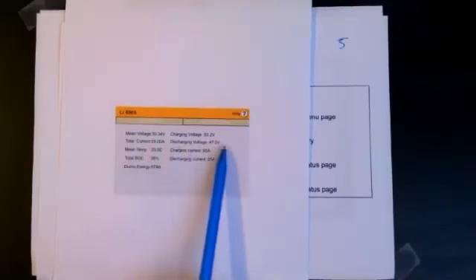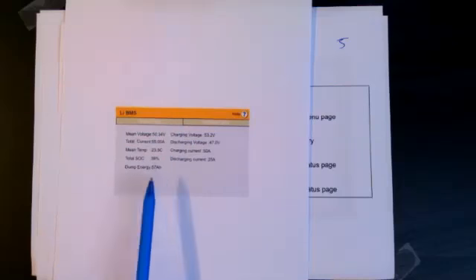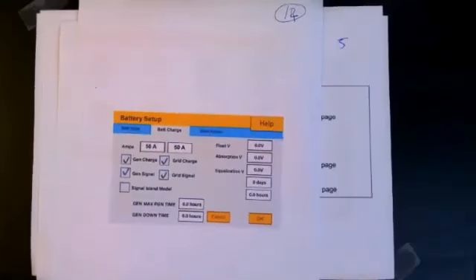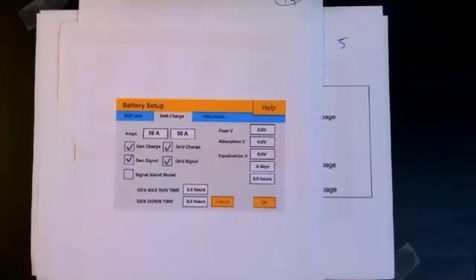You must make sure that you get something like this. You will see a very clear message, and this information is coming from the BMS, the battery management system. If you don't get a very clear message like this, then you've got a problem. And this happens a lot. A lot of people don't realize the importance of the communication. Now, if you're going back onto your battery here and it can't communicate, we've just got a list of all the batteries that we recommend. There are lots of batteries we recommend, but we don't mean that all lithium batteries can communicate with our inverter.